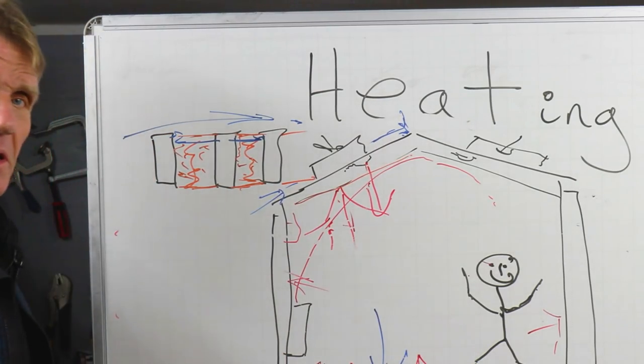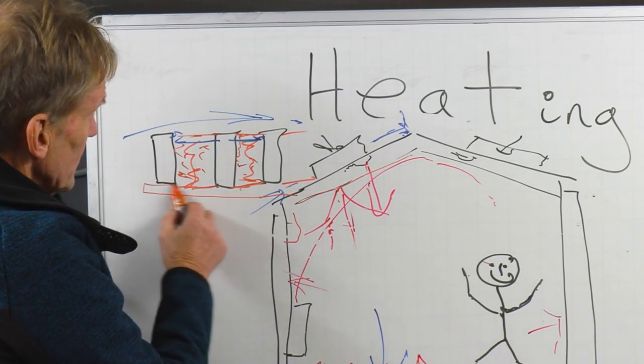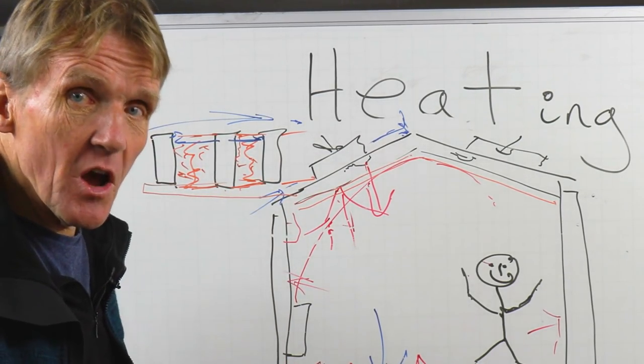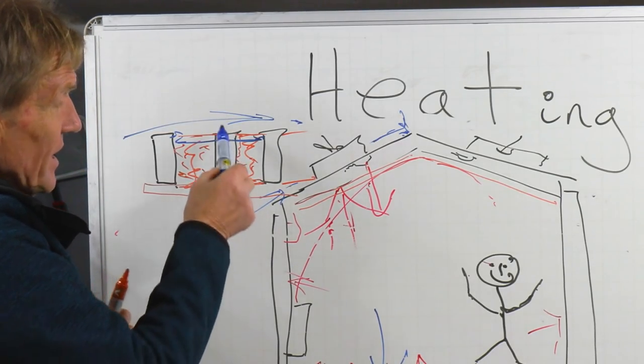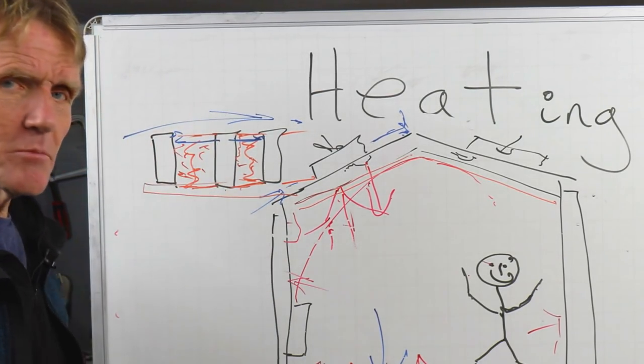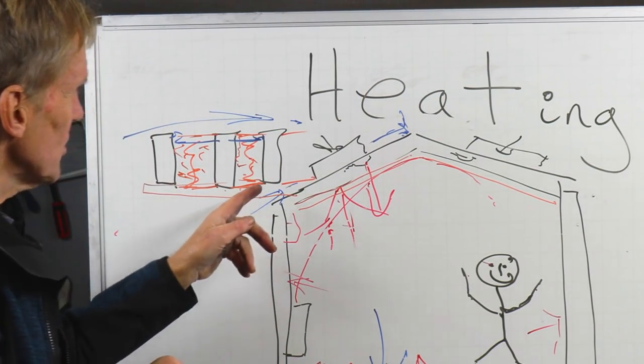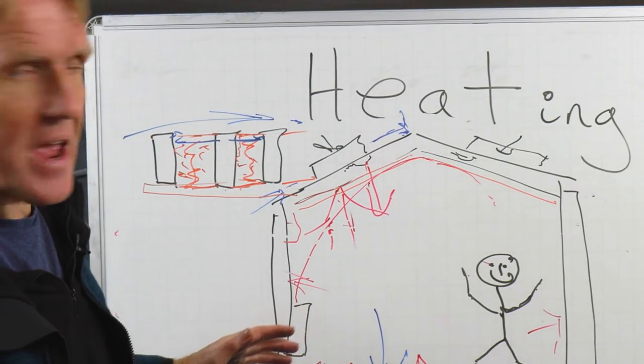If you can imagine, those rafters are stuck around that way, so what we've got is a level face. Now, not the end of the world, because we also have very often a sheet of insulation going right underneath those rafters. So in other words, it would be going right up there and right down there, covering all those rafters to stop what we call cold bridging. Now, cold bridging obviously is conduction. That's how the heat's escaping. It's escaping through the conduction, and even though that's timber and it's not a great conductor of heat, it will conduct some, and you get these cold spots, and sometimes you can even see them. When you look at a ceiling, sometimes you can see the marks where the heat is different, and you can see maybe a little bit of condensation formed on there or whatever, but you will see a difference. So that situation there, where we have a sheet of insulation underneath, maybe 25 millimeters thick, is a great idea.